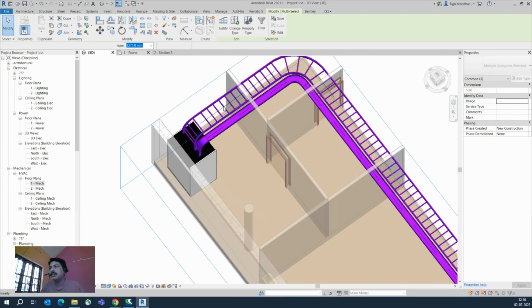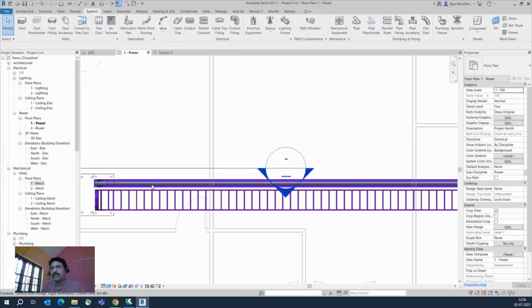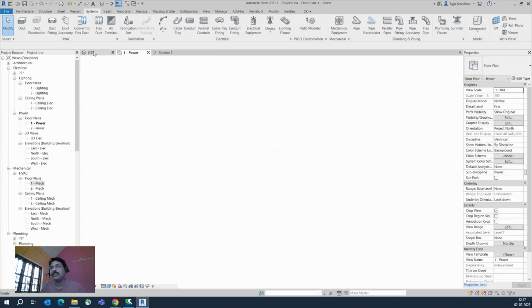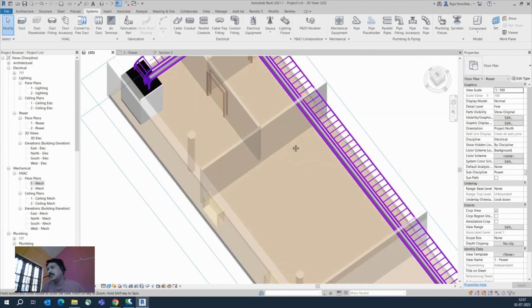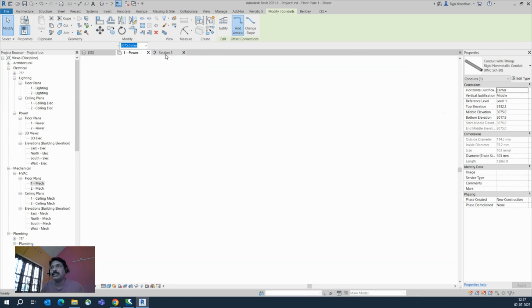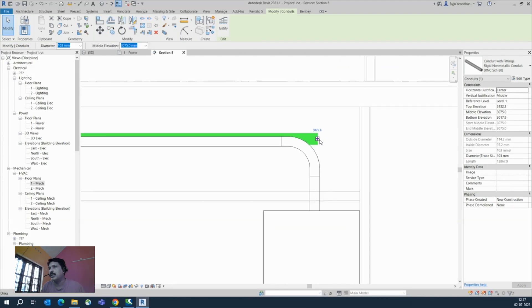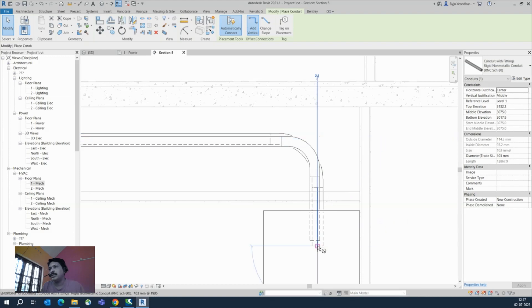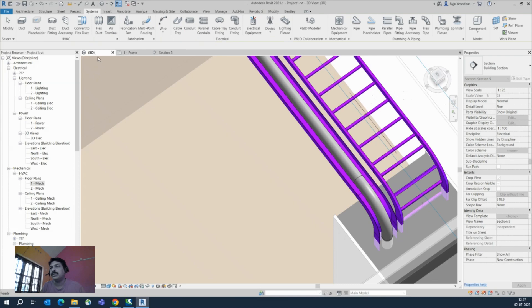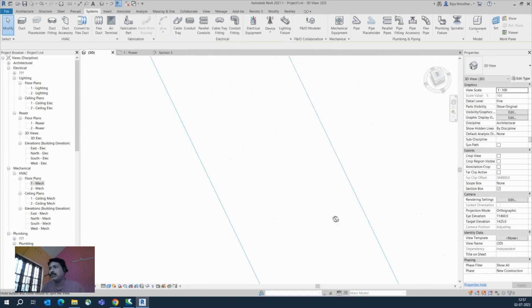You may notice the height is different. Click on the conduit — it is at elevation 2275. We need it at 3075 to match the cable tray level. In the 3D view you can see the conduits running to the cable tray. Then in the section view, drop the conduits down to the panel the same way. You can see the conduit is dropping down to the panel.